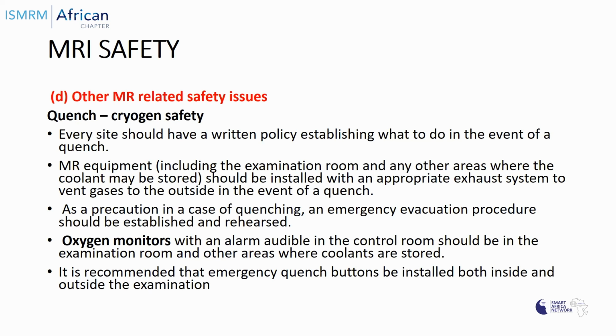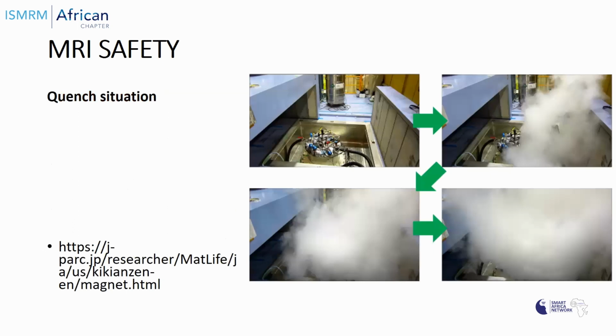Oxygen monitors with an alarm audible in the control room should be in the examination room and other areas where coolants are stored. It is also recommended that emergency quench buttons be installed both inside and outside the examination room. This is an example of a quench situation I picked from the internet. You can see the helium gas coming out and how serious it is.